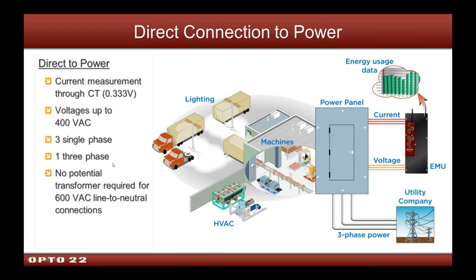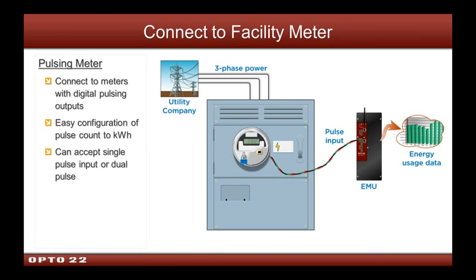So now let's look at a utility meter. That's a very simple connection. You basically have either a 2-wire or 3-wire situation, single output or dual, and we take those directly into DI inputs on the OptoEMU sensor. And the way that that's done, I'll get into a couple of screens where we show how the configuration is done, but your utility will tell you what one pulse represents as far as kilowatt hours, and we go ahead and scale that in the OptoEMU sensor configuration screens.